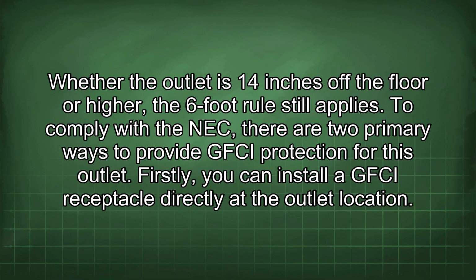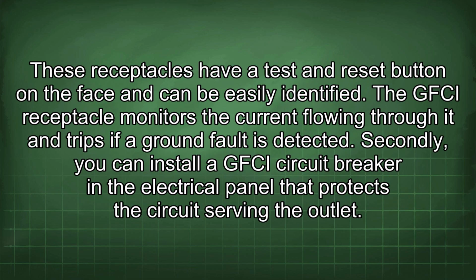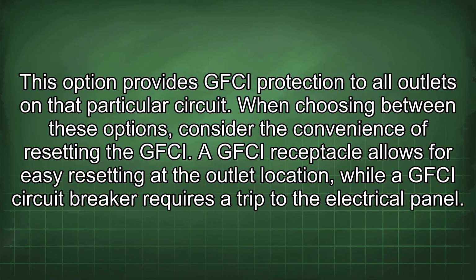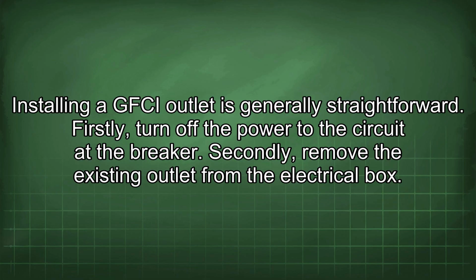To comply with the NEC, there are 2 primary ways to provide GFCI protection for this outlet. Firstly, you can install a GFCI receptacle directly at the outlet location. These receptacles have a test and reset button on the face and can be easily identified. The GFCI receptacle monitors the current flowing through it and trips if a ground fault is detected. Secondly, you can install a GFCI circuit breaker in the electrical panel that protects the circuit serving the outlet. This option provides GFCI protection to all outlets on that particular circuit. When choosing between these options, consider the convenience of resetting the GFCI. A GFCI receptacle allows for easy resetting at the outlet location, while a GFCI circuit breaker requires a trip to the electrical panel.